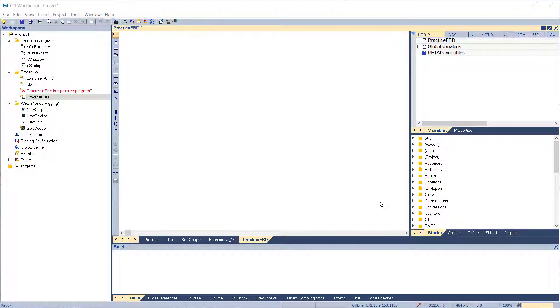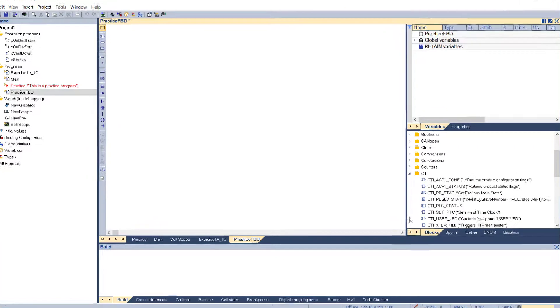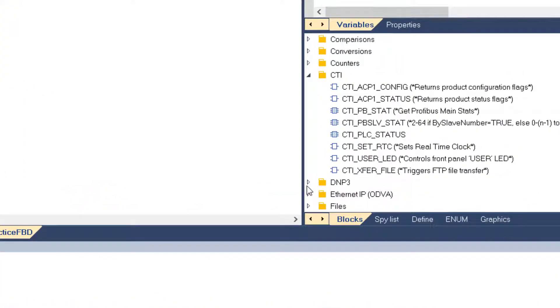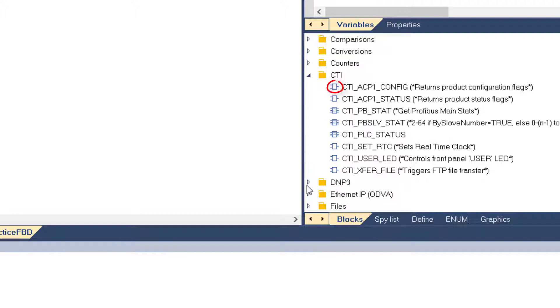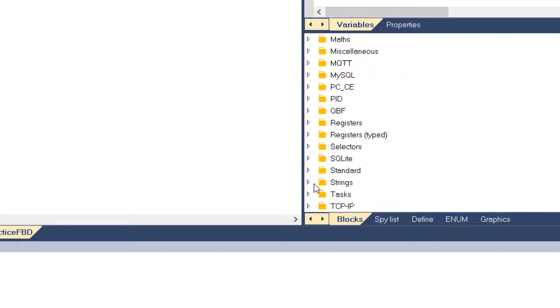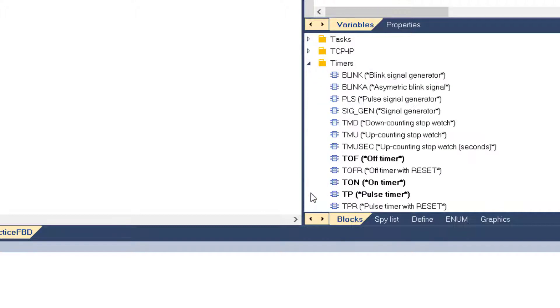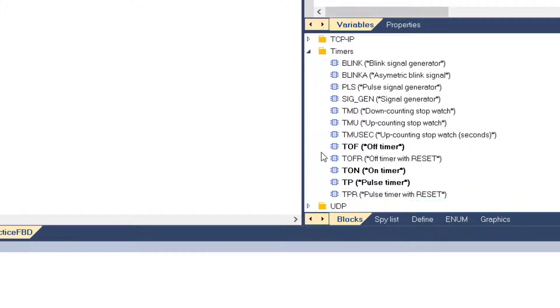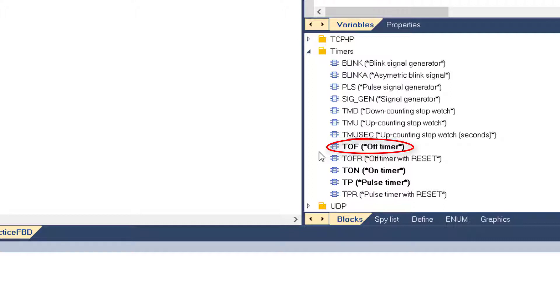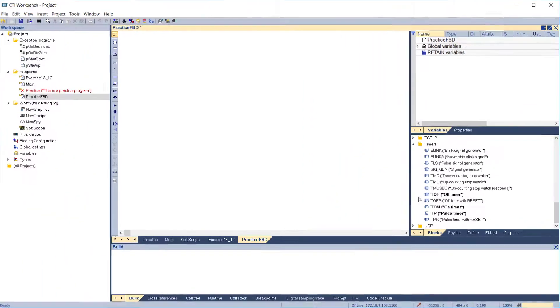When looking through the list of objects, you'll notice two different icons used next to the name of the objects. The icons which are filled in are function blocks. The non-filled icons are functions. You may also notice that some objects are bolded. This means they are IEC 61131 standard functions or function blocks. Using the bolded ones, where possible, could make it easier to convert your programs to another IEC 61131 implementation from a different manufacturer.